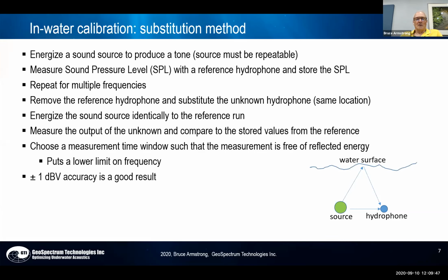So the way that you calibrate a hydrophone normally is you put both in the water, that's as deep of water as you can find. You energize a sound source to produce usually a tone. You measure the sound pressure level with a reference hydrophone, and you store all the sound pressure levels that you've measured. And then you repeat that for multiple frequencies. Then you remove the reference hydrophone, you substitute the unknown hydrophone in the same location, and then you re-energize the sound source in the same way that you did on your reference run. And then you just compare your unknown outputs to the stored values from the reference, and you have a sensitivity curve versus frequency.